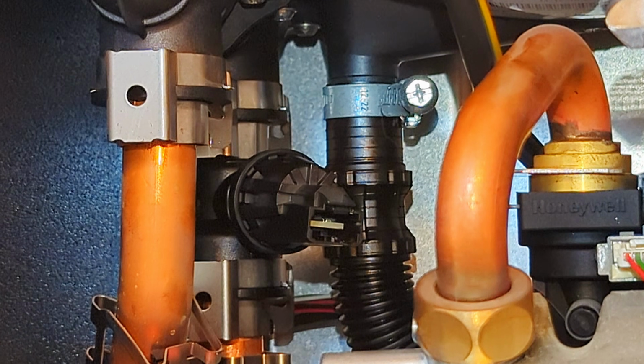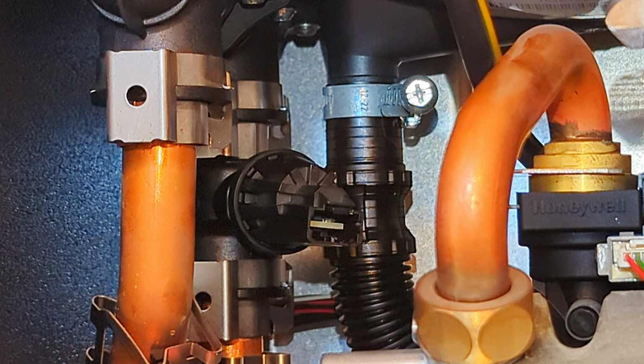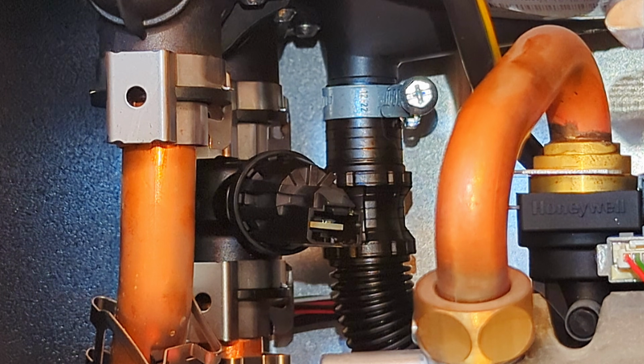Now I give the pressure sensor a good tug again, trying to pull it out, just to make sure that clip is retaining the pressure sensor correctly. Because trust me, you do not want that thing bursting off and spraying water all over your electrical components in the boiler.